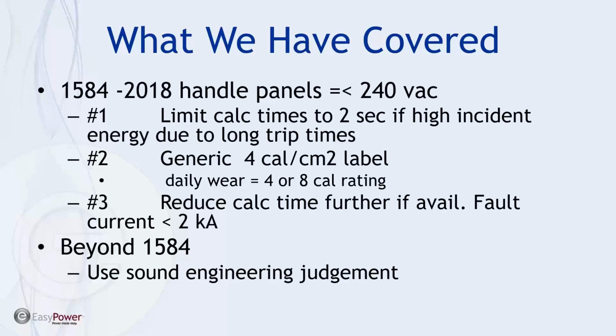Okay, Luis is saying he's been observing in the IEEE documents the arc duration time and opening time, and asks that they be explained. So the arc duration time is a combination of, in the case of a breaker or a switch that's being triggered by a relay, the opening time includes the relay response time plus the opening time of the breaker. In a solid state low voltage power circuit breaker, that trip unit is included in the TCC curves that the manufacturer releases. And so you have a width of the curve that gives us some variation in time.